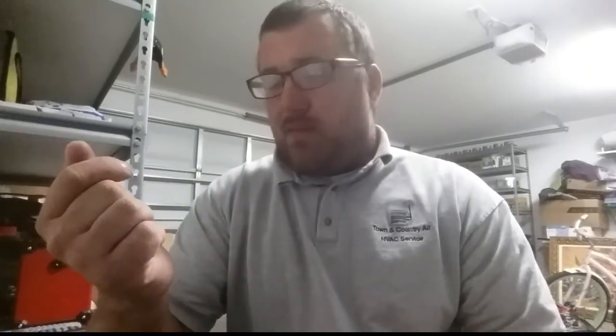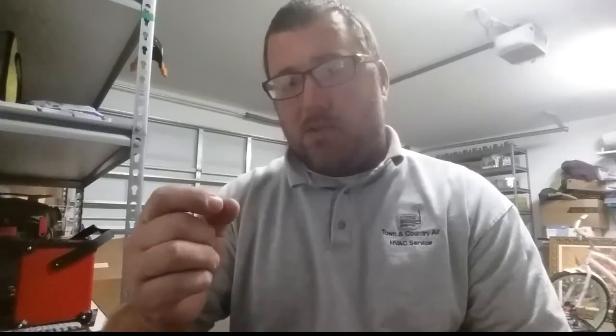Now if you have an overcharge, you'll flood the coil with excess refrigerant, have a low superheat, and have a high suction pressure. Because basically the machine is overfilled. Imagine, like anything else, it's hard to evaporate if you have very close molecular space. Meaning, if you imagine all these objects, even the air has a certain temperature. Its temperature is created just by molecular motion. The hotter it is, the faster the stuff moves. It's just a whole bunch of stuff in the air moving very quickly.